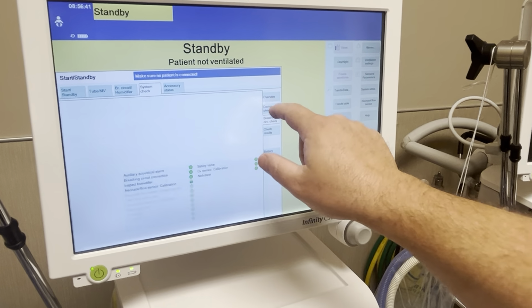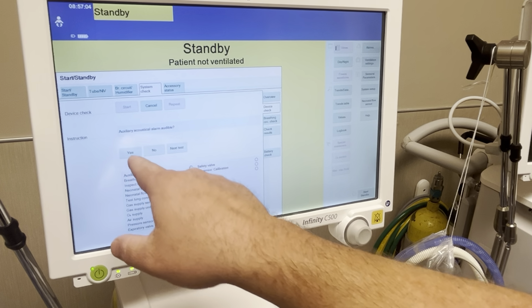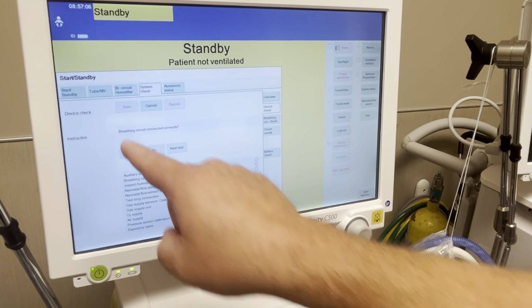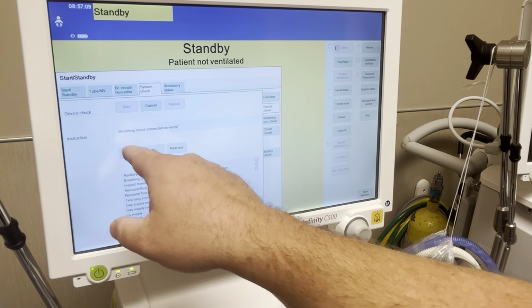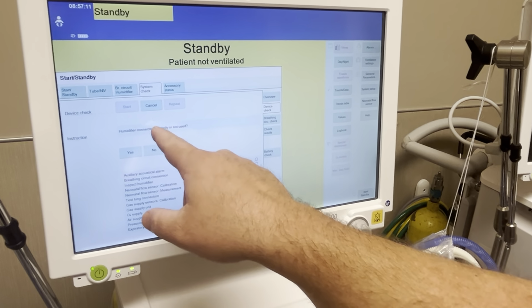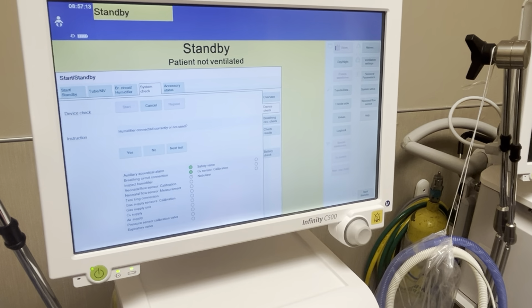But you want to do this every time you start it with a new patient. So we'll start, and you got to confirm it just like everything else. It'll ask if you hear an alarm, which you can hear, so you hit yes. Breathing circuit connected correctly, yes. Humidifier connected correctly or not in use. So yes, it's connected. Now it says test lung removed and neonatal flow sensor occluded.